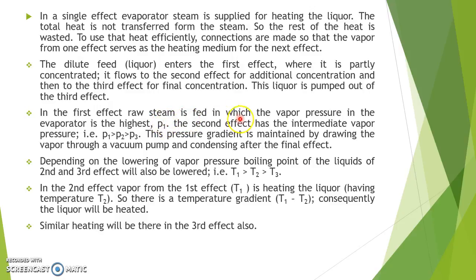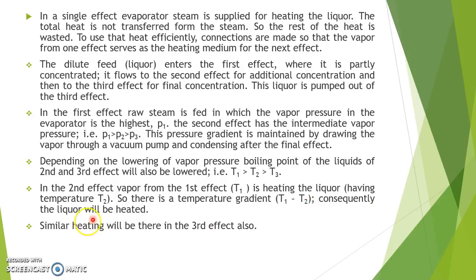In the first effect, raw steam is used, in which the vapor pressure in the evaporator is the highest — p1. The second effect has an intermediate vapor pressure, giving p1 greater than p2 greater than p3. This pressure gradient is maintained by drawing the vapor through a vacuum pump and condensing after the final effect. Depending on the lowering of vapor pressure, the boiling point of liquids in the second and third effects will also be lowered. In the second effect evaporator, vapor from the first effect at temperature T1 heats the liquor at temperature T2, giving a temperature gradient of T1 minus T2. Consequently the liquor will be heated, and similarly heating will be done in the third effect.